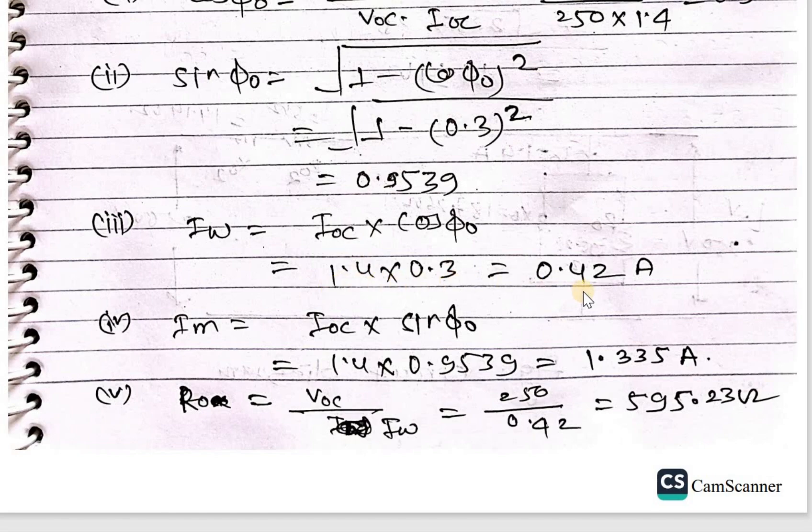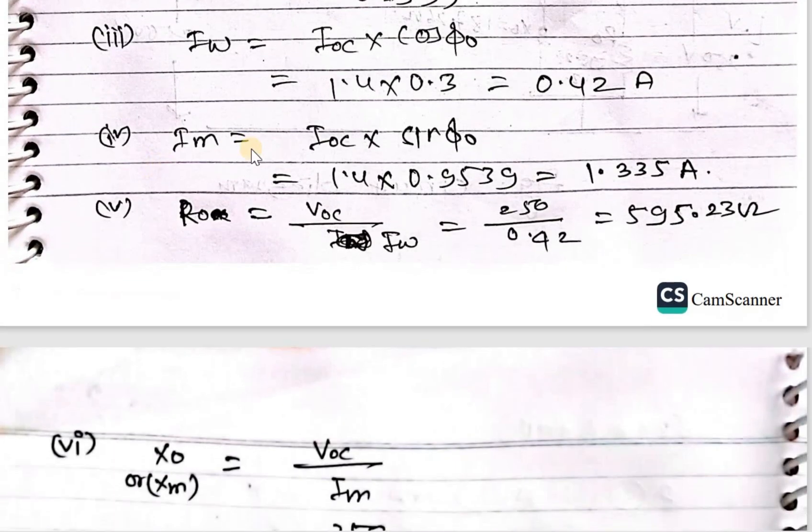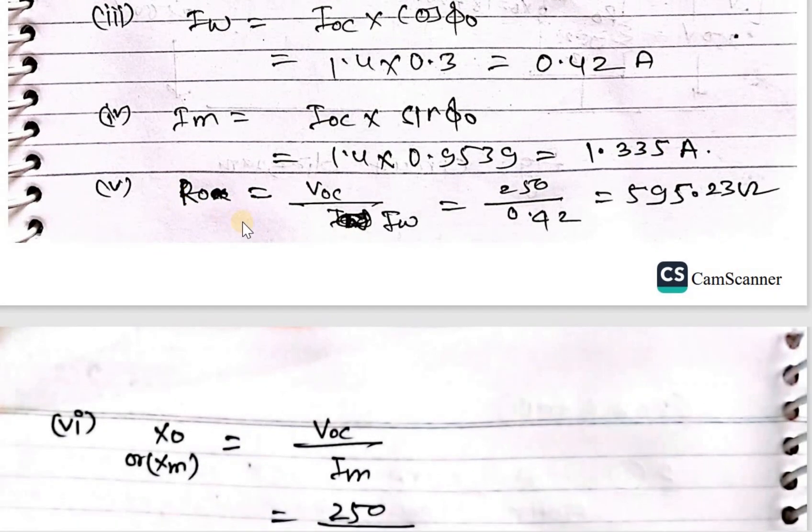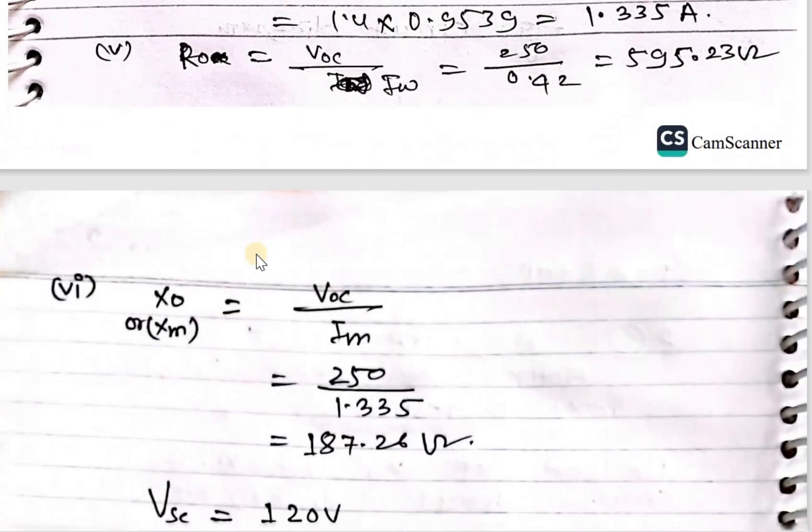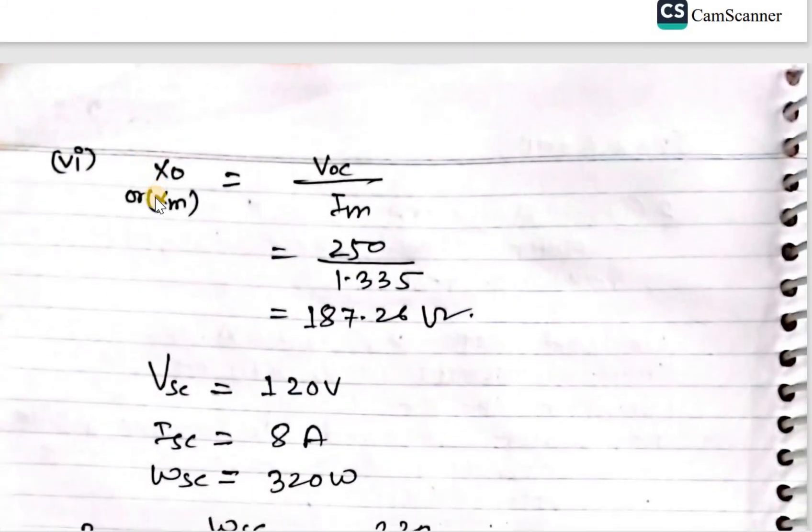Im equals 1.335 ampere. R0 equals Voc upon Iw, that is 250 upon 0.42, 595.23 ohm. And X0, or we can say Xm, equals Voc upon Im, 250 upon 1.335, that is 187.26 ohm.